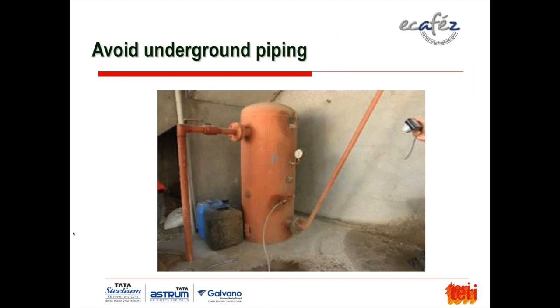Another typical mistake in compressed air pipelines is having underground piping. As this photograph shows, after the receiver it goes straight underground. If it is underground, then even if there are leakages because of corrosion of the pipeline, after a few years you'll never notice it. So this is to be avoided, and it should always be overground piping for a compressed air network.